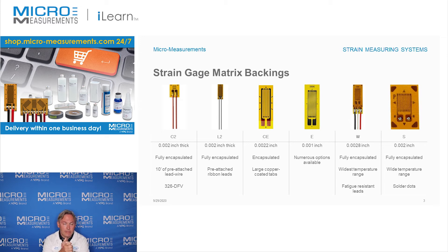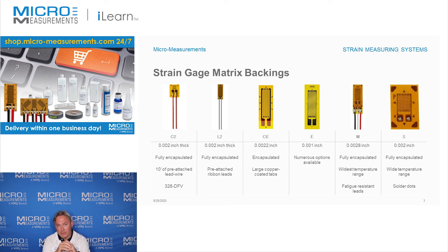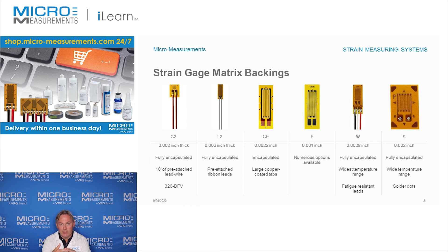CE backings are widely used in industry for general purpose stress analysis testing. They are available in a wide variety of sizes, all the way down to a 0.015 inch gauge length, and in CE construction you can get gauges up to 0.5 inch active gauge length. All geometries are available in CE construction: uniaxial, T rosettes, shear patterns, rectangular rosettes, and even delta rosettes.